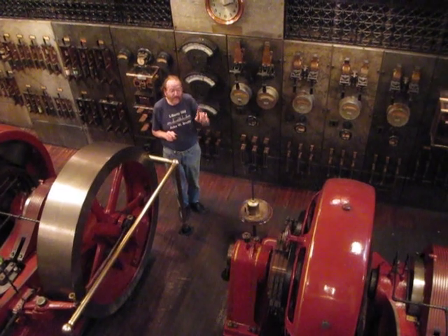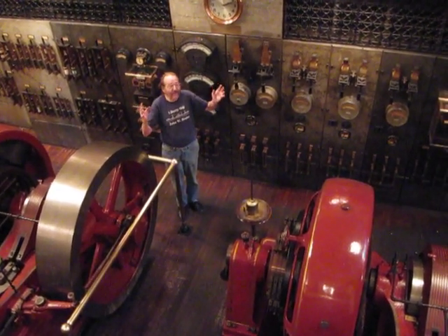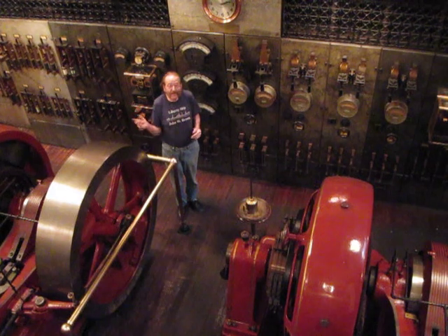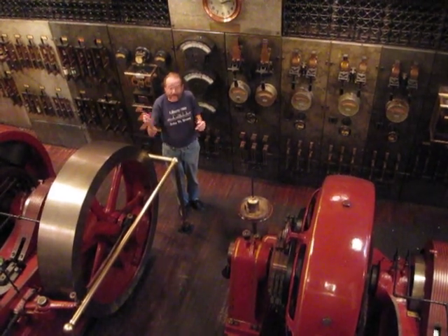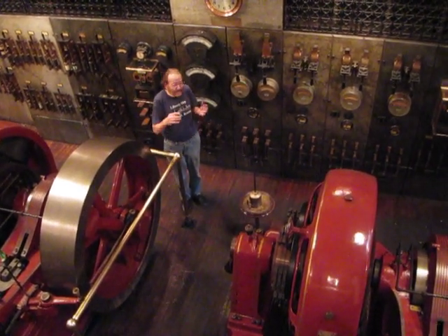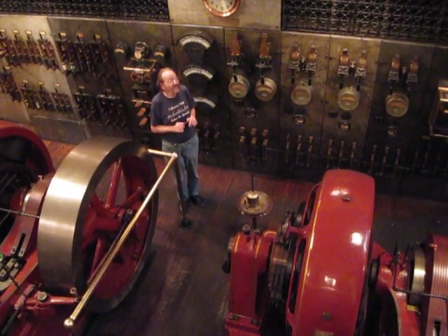In a sense, the weather may suddenly turn warm and we decide we don't need two boilers and shut one down. It may go the other way — all of a sudden by mid afternoon it may drop, as it does in November and December, and you'll have a big problem with the steam pressure and then you have to start more boilers. So we're constantly turning things on and off based on the load.